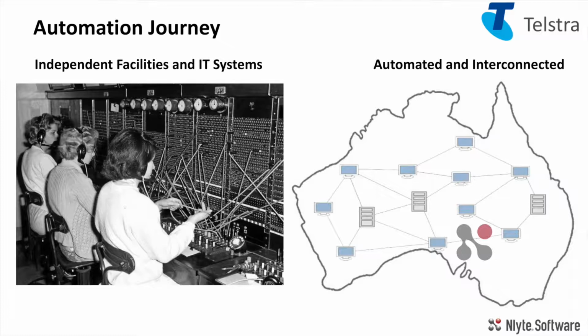So when something changes in your environment, if we talk about cooling, for example, when you've got variable speed fans within your CRAC units or your cooling units, and you have a third-party system to control those fans depending on air temperature, you can integrate Nlyte into that stack, or you can use Nlyte to pick up the details around what that cooling stack and the IT stack that controls it are doing, and then plug that into Nlyte, integrate it, and you can understand the automation that's happening and see how it's working. Which has been really good.